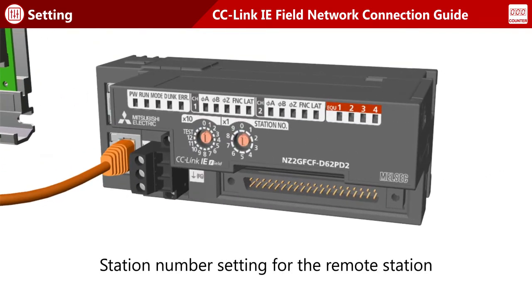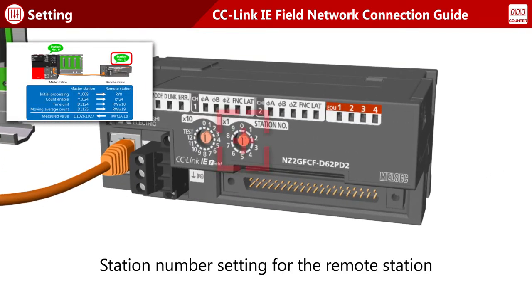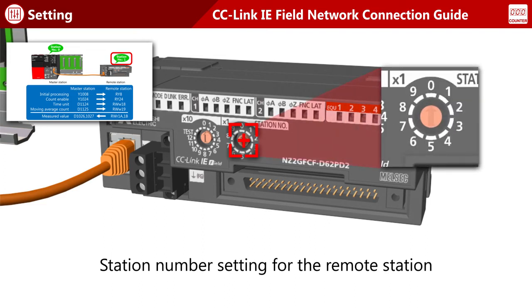Station numbers for remote stations are set using the switch on the front of the module. The remote station is station number one, so set the station number to one using the single digit switch.